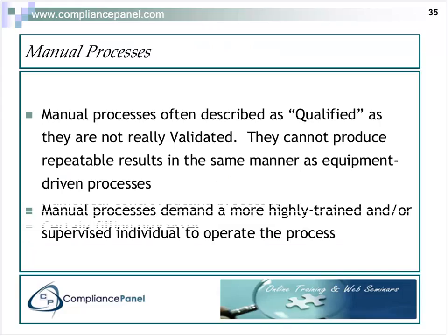Manual processes I indicated are described as qualified as they're not really validated. You can't produce repeatable results in the same manner as equipment-driven processes because there's a degree of variability here between operators, between shifts, between times of day, before lunch, after lunch, all those kinds of things fit into it.